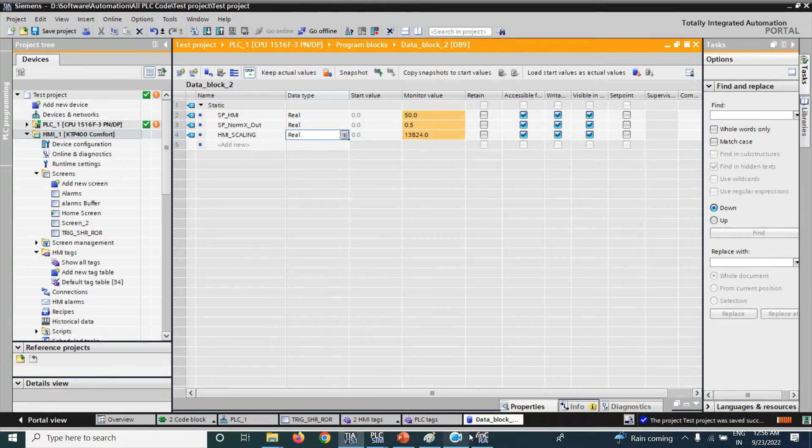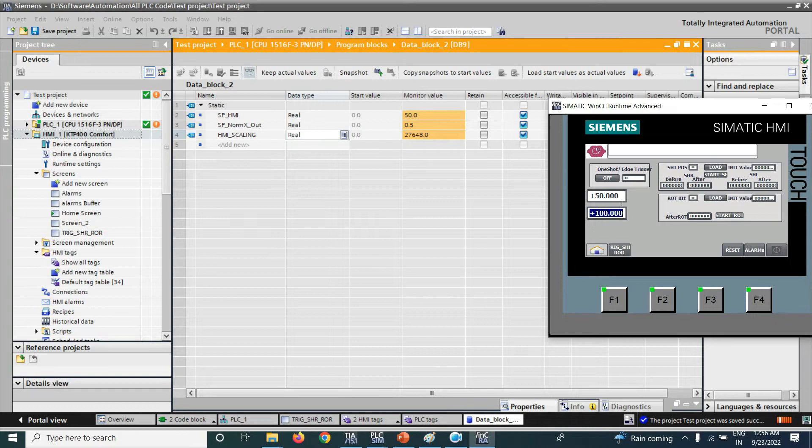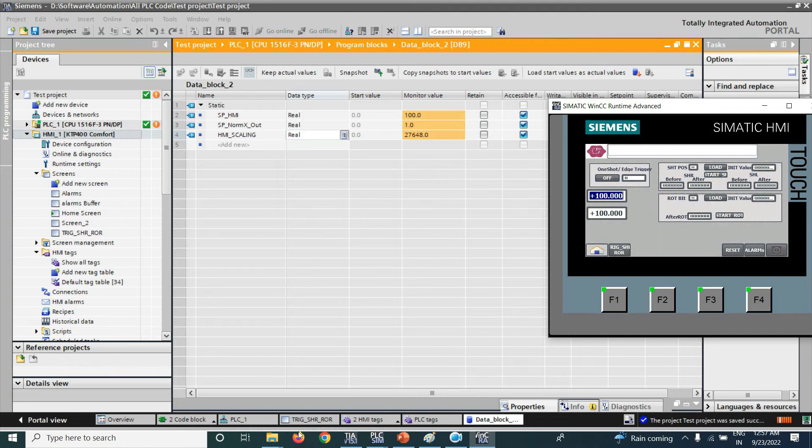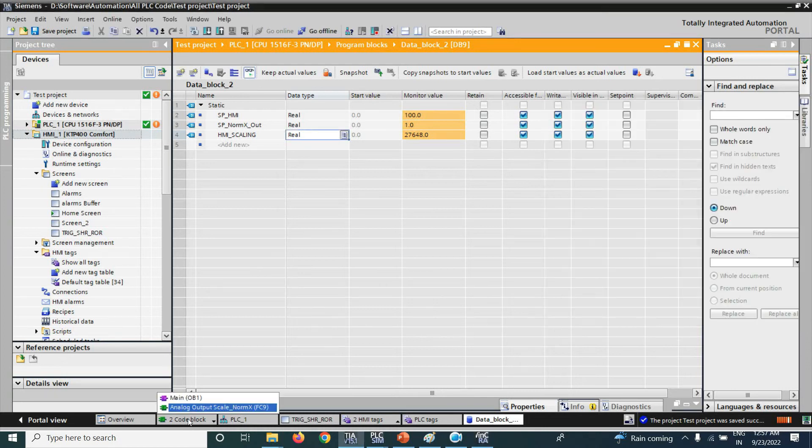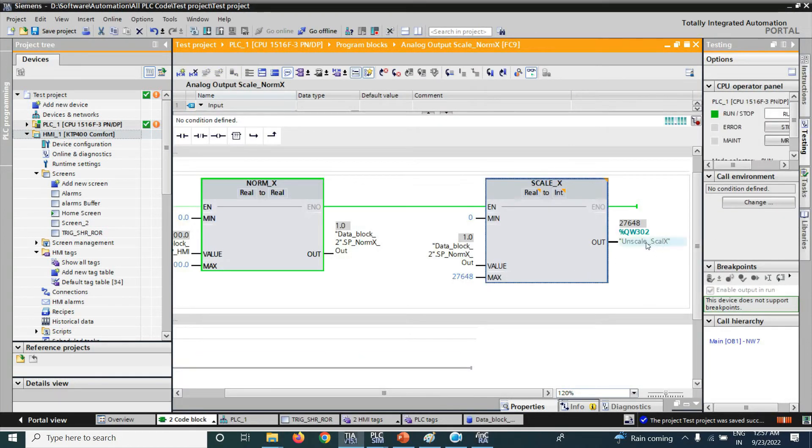If I give 100% setting here, we can see HMI scaling function 27648. And here, also, if I give setting as 100%, then you can see here, the NORM_X and SCALE_X function output also 27648.